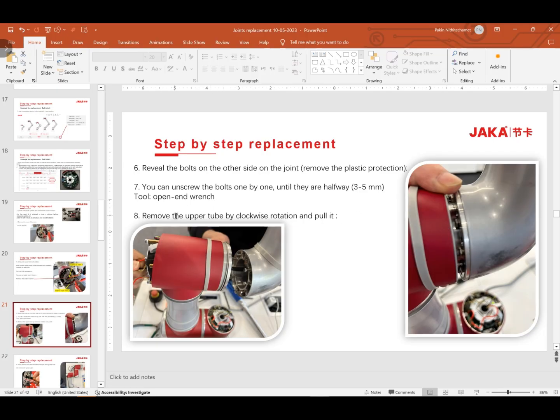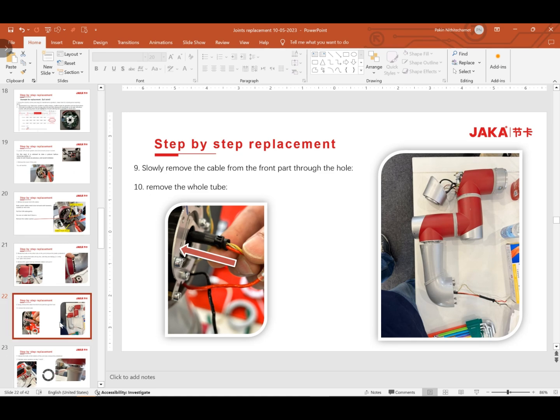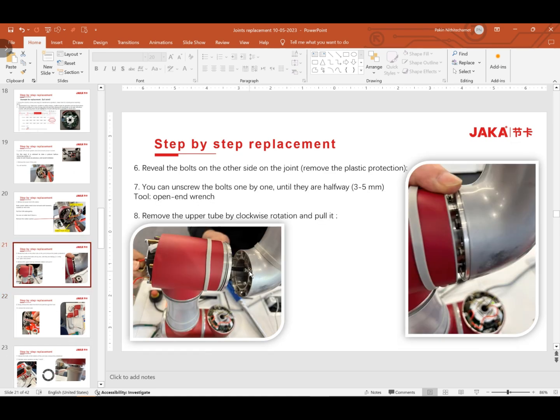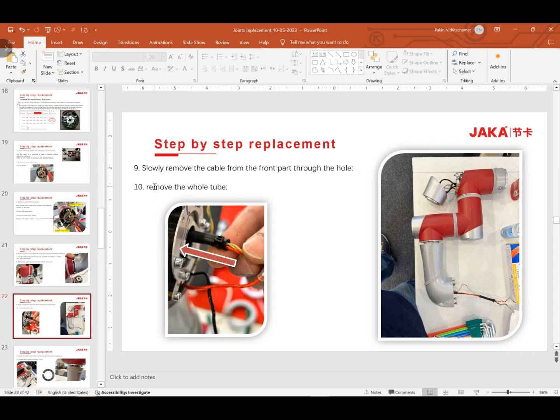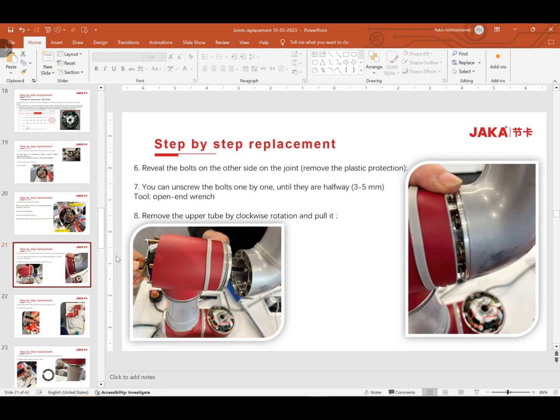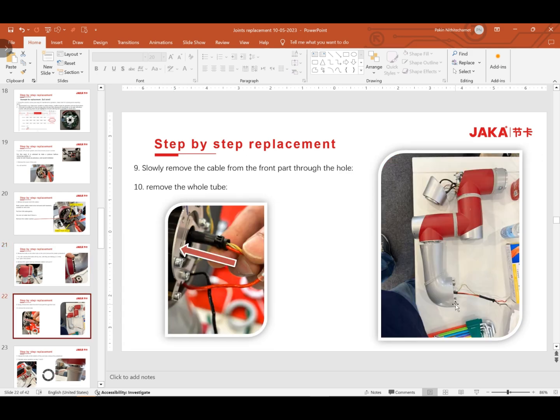And then we remove the upper tube by clockwise rotation and pull it out. When removing, you may see the O-ring here. So basically when we remove the joint, you get a new O-ring also. And slowly remove the cable, because when we pull it out, you can see there is cable here that aligns with the joint, so you need to pull it out from this direction. After you pull it out, you will see this one.